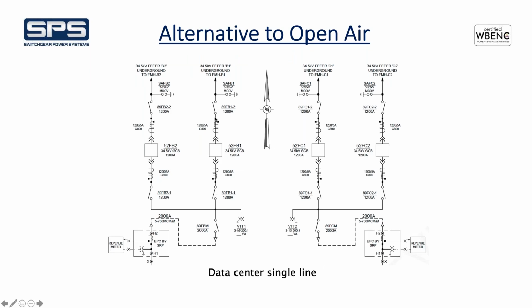Line and load. So definitely. But metal clad, there will be no way to have those 2 disconnect switches incorporated. Is that right? Correct. Not on metal clad. It has to be a metal enclosed design. You're correct. Okay.